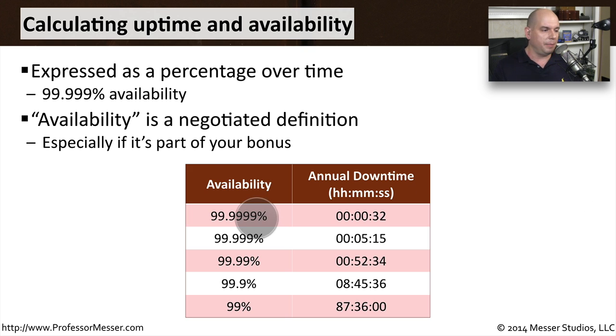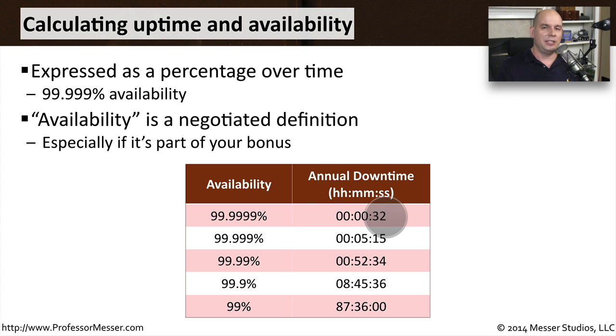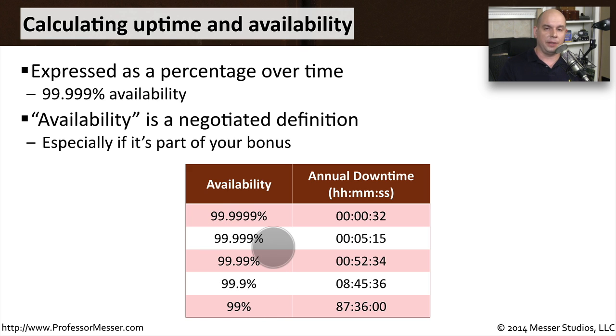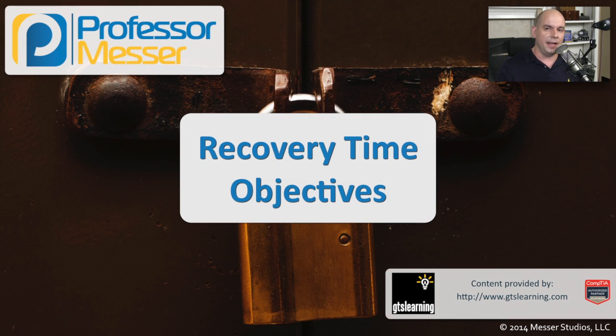If you have availability of 99.9999%, that means your actual downtime — usually over an entire year — is 32 seconds. That's a pretty aggressive availability percentage. For five nines, you can only be down for five minutes and 15 seconds during the entire year. And an availability of 99% means that you were down for a maximum of 87 hours and 36 minutes over that entire time frame. You can see the difference between 99% availability and five nines is very large, and it also means you have to have a lot of redundancy and planning in place to achieve five nines of availability.